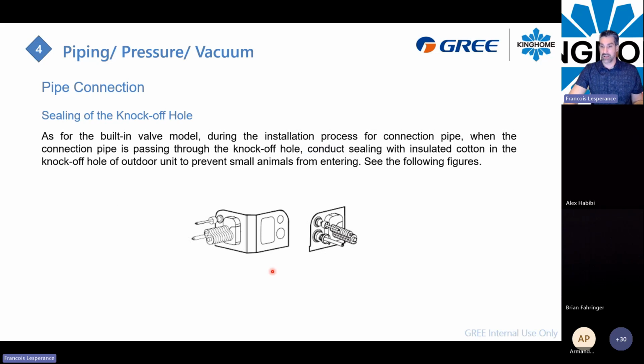On this 3-ton unit, you will also have the knockout hole. So make sure at the end of the installation, when you put on your Armaflex and all the stuff, the knockout hole is properly sealed. And also for your connection cable, the high power and the low power cable, make sure every hole is properly sealed to avoid having a small animal enter the system and bite the wiring and all the stuff. So make sure it's sealed properly.